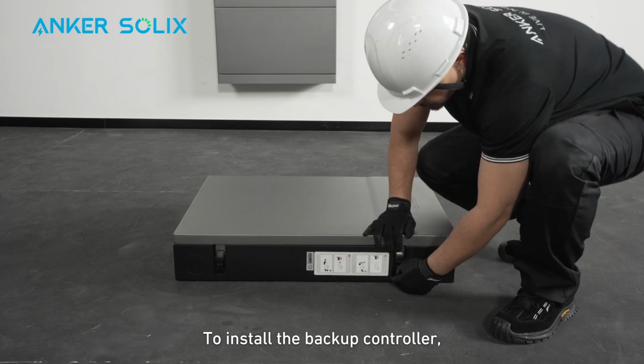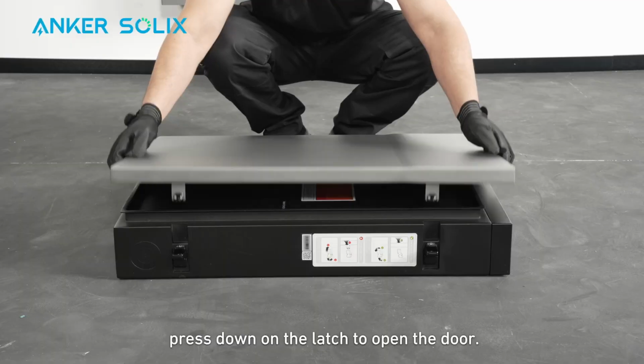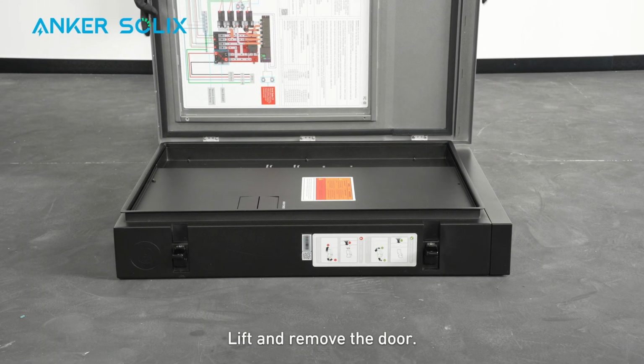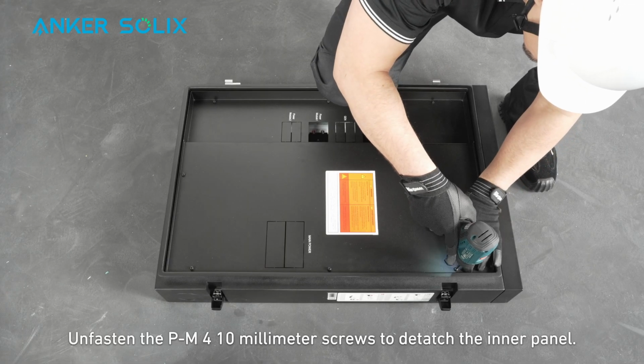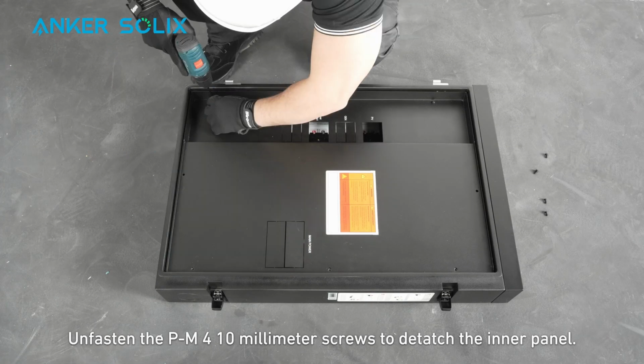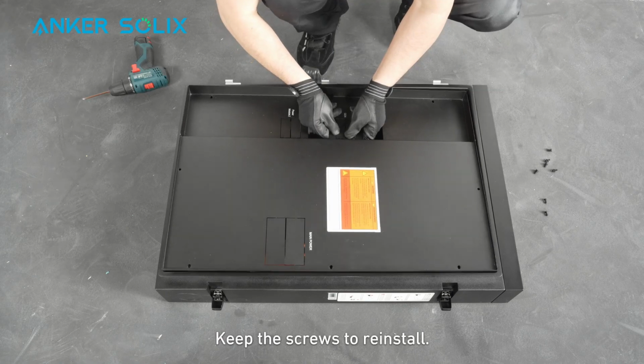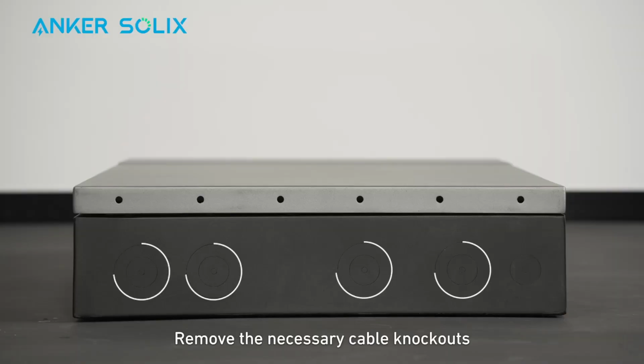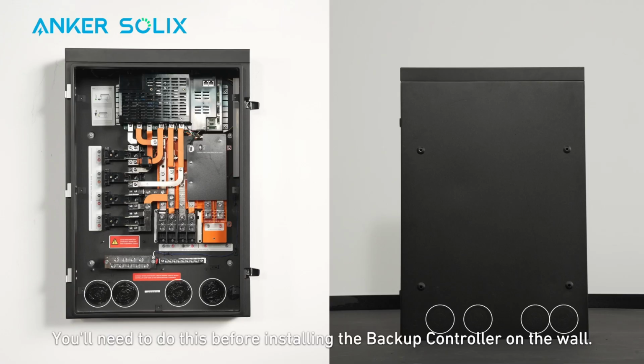To install the backup controller, press down on the latch to open the door. Lift and remove the door. Unfasten the PM4 10mm screws to detach the inner panel. Keep the screws to reinstall. Remove the necessary cable knockouts on the bottom of the backup controller. You'll need to do this before installing the backup controller on the wall.